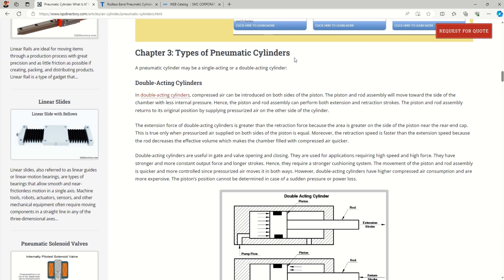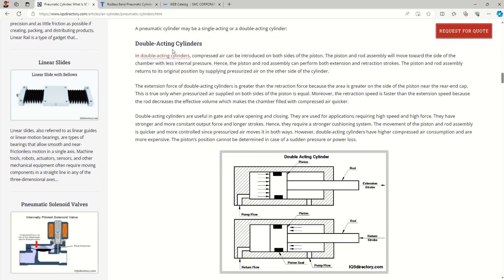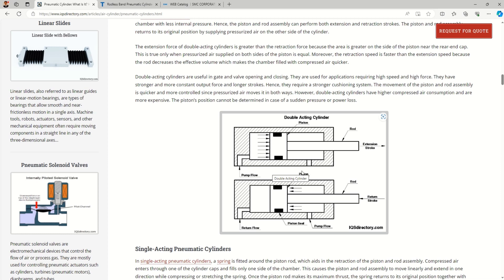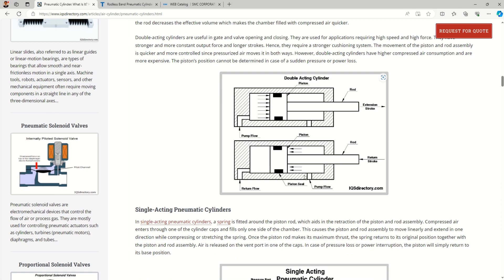The most important and basic type is the double acting cylinder. Looking at the cross-section, we have a port on one side, a piston, and a piston rod, with another port on the other side as the exit. In a double acting cylinder, we pass fluid on both sides. For the extension stroke, we pass pneumatic fluid on the piston side — the force moves the rod forward — and the air from the rod side exhausts from the other port.